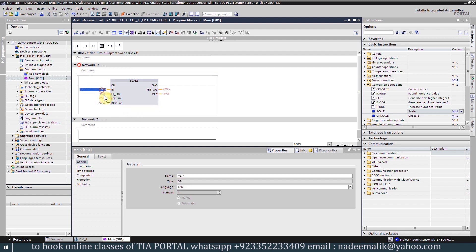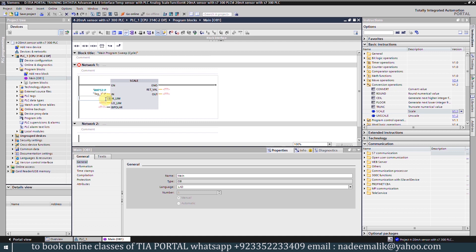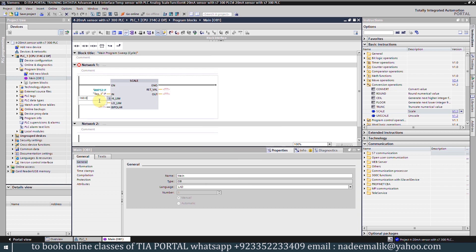At IN we will enter PIW752 which is the input word for channel 0. Next in the high limit we will enter 160.0 as the maximum range of this transmitter is 160.0. In the low limit input we will enter 0.0.